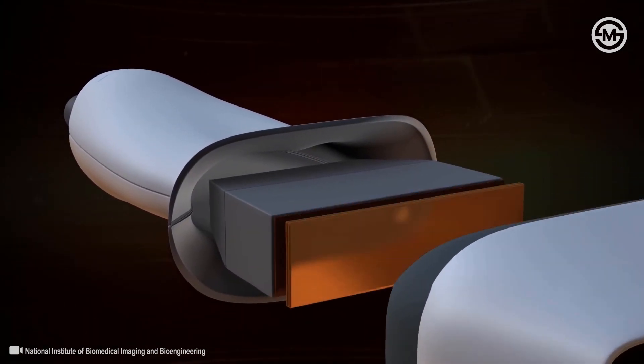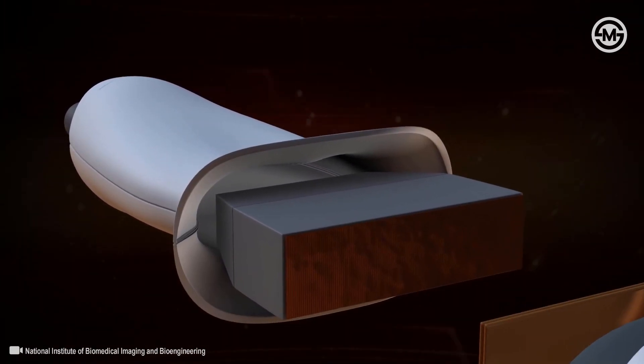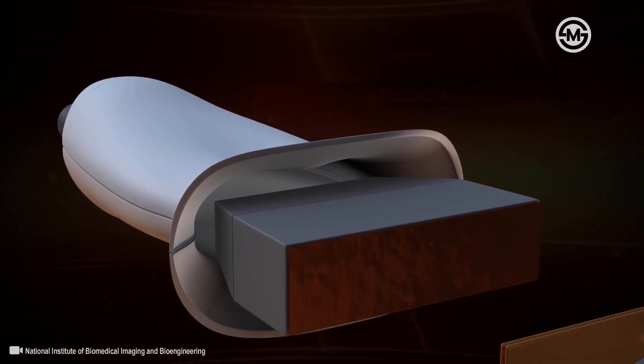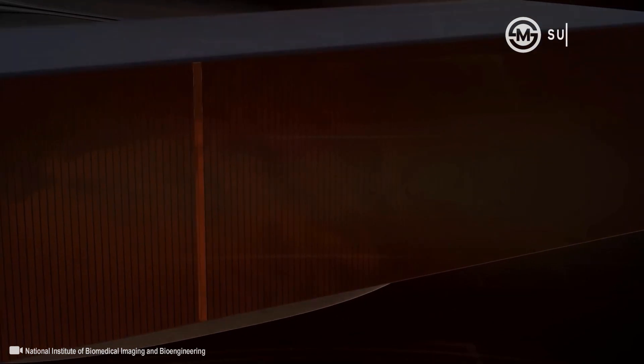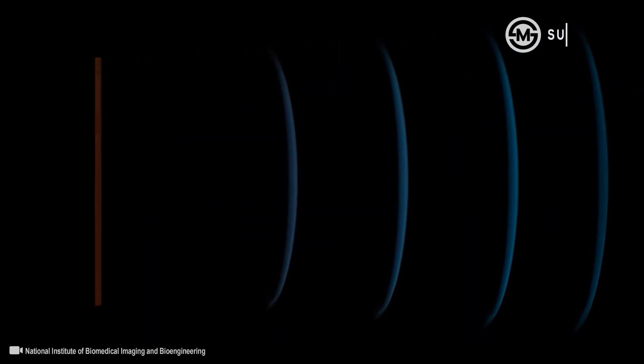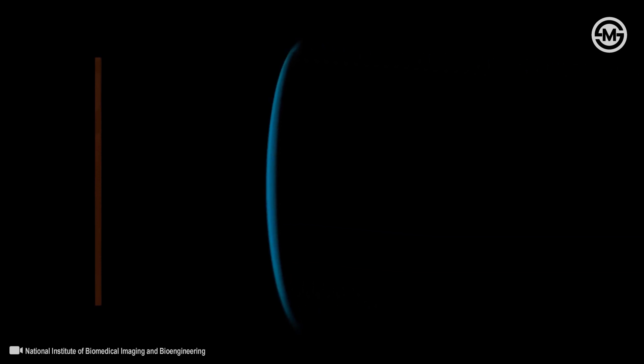The heart of most ultrasound systems is a device called a transducer, which uses an array of piezoelectric crystals. A piezoelectric crystal vibrates when an electric signal is applied, producing high-frequency sound pressure waves, which we call ultrasound. More importantly, this type of crystal can also work in reverse.